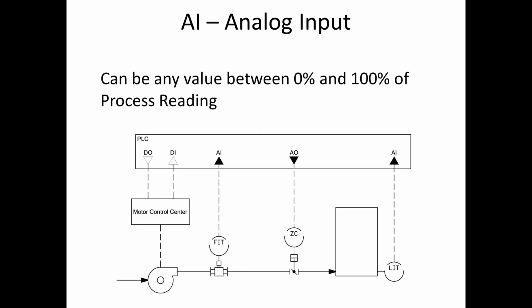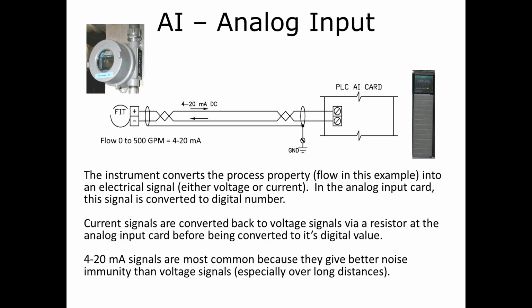And the same way we talked about multi-state outputs. The analog input is a little different, in that it gives you a value somewhere between 0 and 100%. So for example, let me just go on to the next slide. This is a diagram of a flow indicating transmitter, a flow meter, and it is ranged from 0 to 500 gallons a minute. What that does is it sends a corresponding 4 to 20 milliamp signal to the PLC card that takes that value and converts that milliamp signal into a numerical value. And once again, you notice that the difference between 4 and 20 is 16.